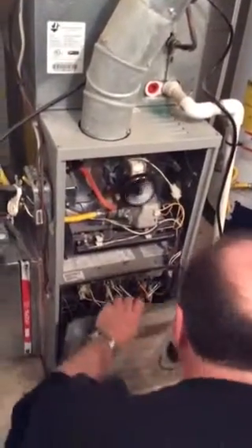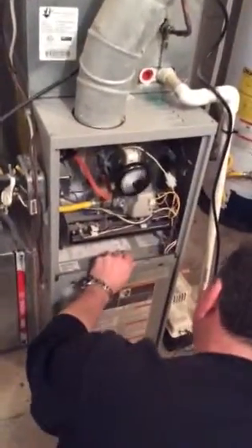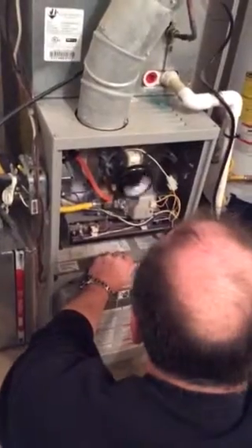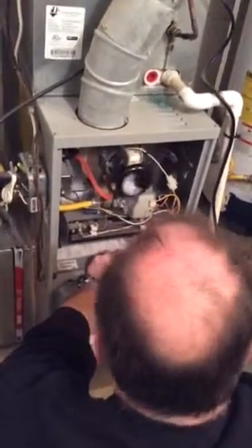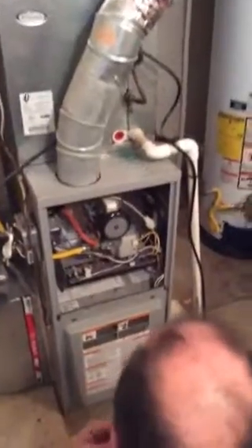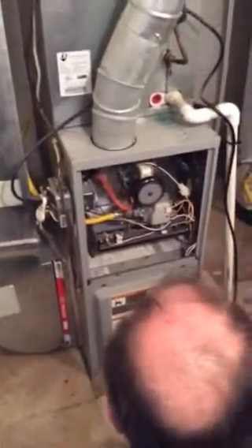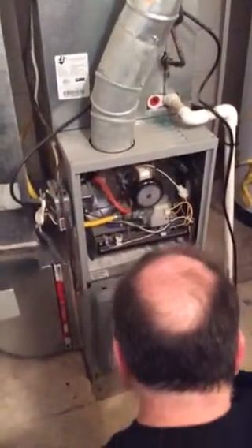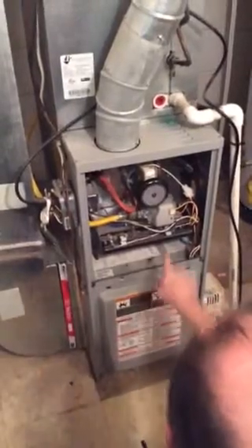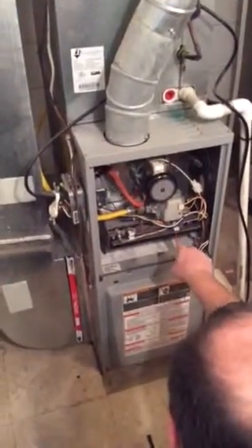So the ignition sequence goes like this. When the furnace is getting ready to start, the first thing that happens is this little fan starts to run, like it's doing right now, doing a little diagnostic test. It's making sure there's a clear path to send the exhaust gas, then it sends a signal down to the computer board. The next thing is the computer sends a signal to ignite the electronic igniter down in here. It's usually like an orange glow that you see back in there right now.